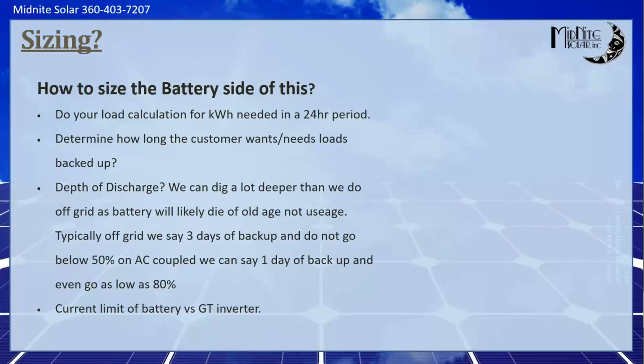And again, it comes back to that. The battery is going to age out before it wears out. So we may go ahead and beat that AGM down to 25% state of charge instead of 50 to save that customer some initial investment because they're not going to wear that battery out. They're going to age that battery out. But if the customer is doing a system that is sort of like semi off grid, then you have to follow all the normal rules because now you are going to wear that battery out versus aging it out.